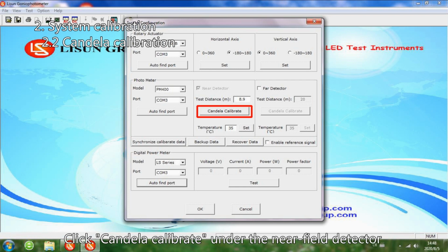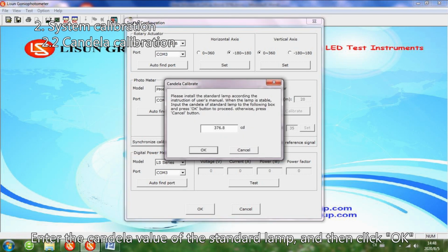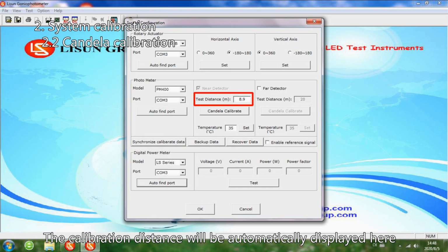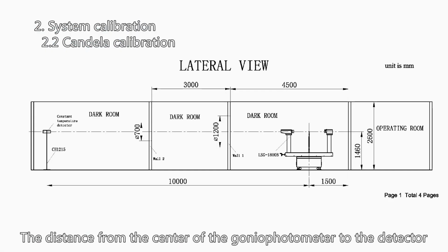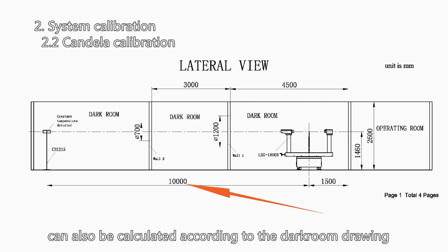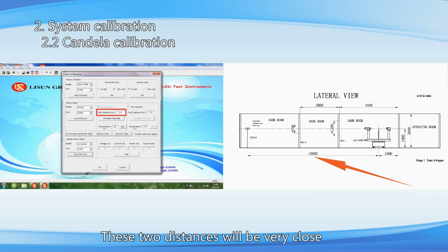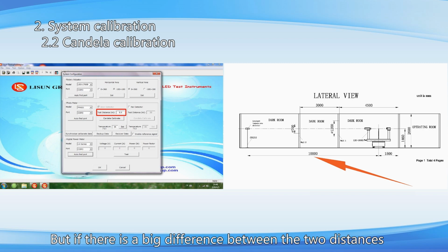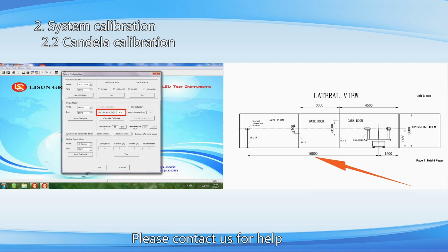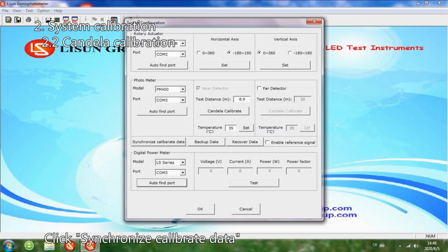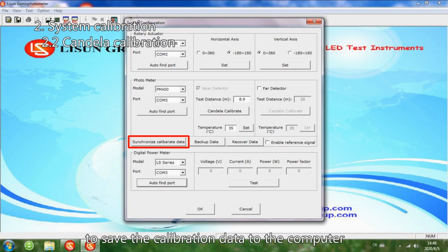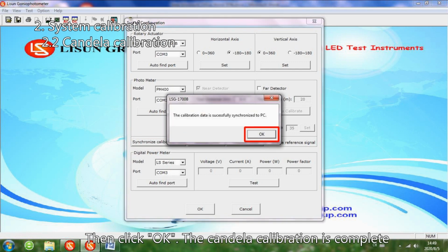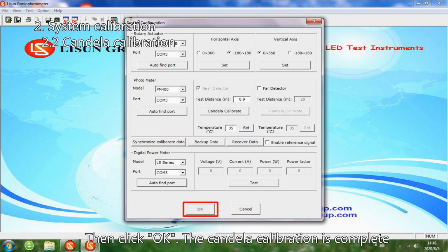Click Candela Calibrate under the near-field detector. Enter the candela value of the standard lamp, and then click OK. The calibration distance will be automatically displayed here. The distance from the center of the goniophotometer to the detector can also be calculated according to the darkroom drawing. These two distances will be very close, but not exactly the same, which is normal. But if there is a big difference between the two distances, please contact us for help. Click Synchronize Calibrate Data to save the calibration data to the computer. Then click OK. The Candela calibration is complete.